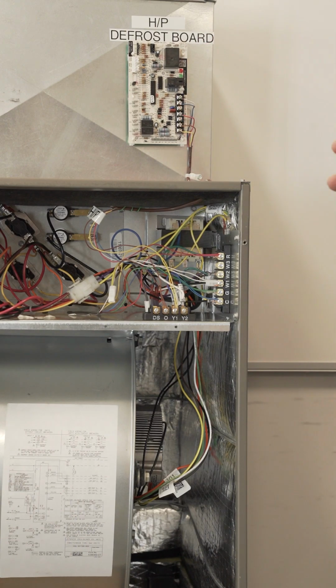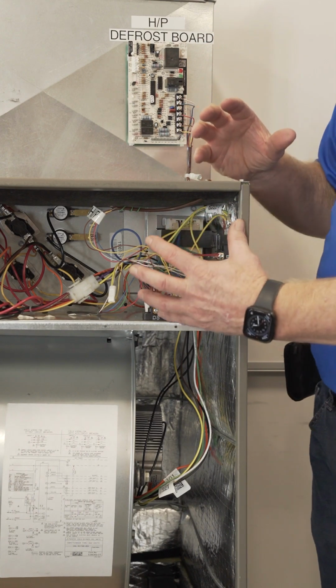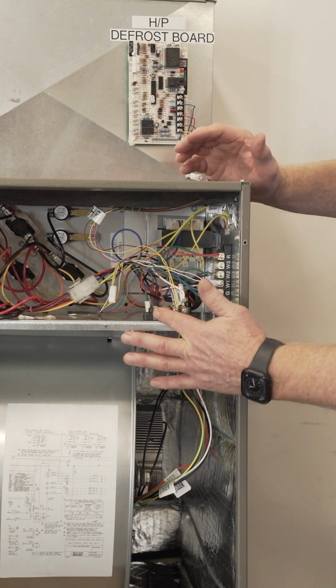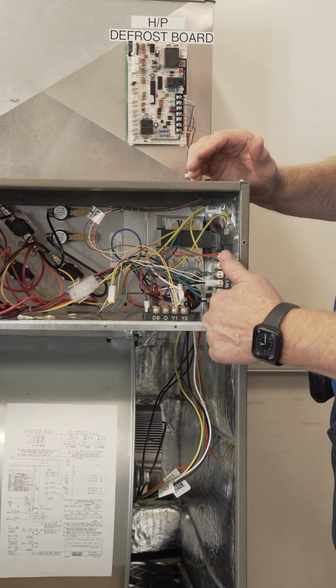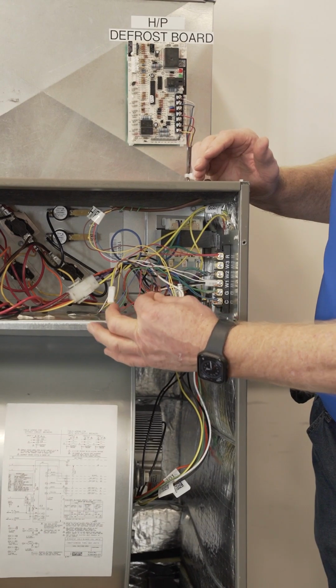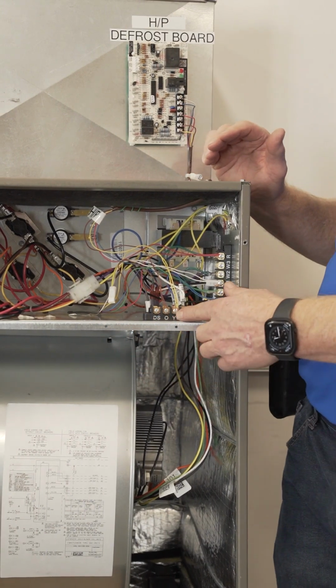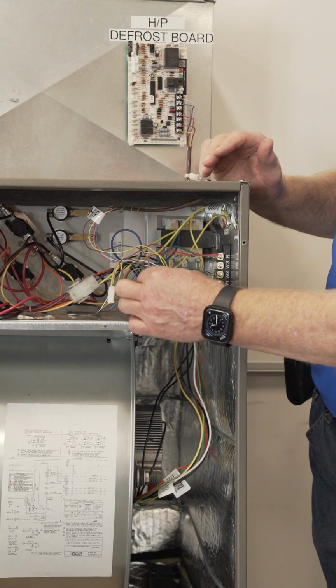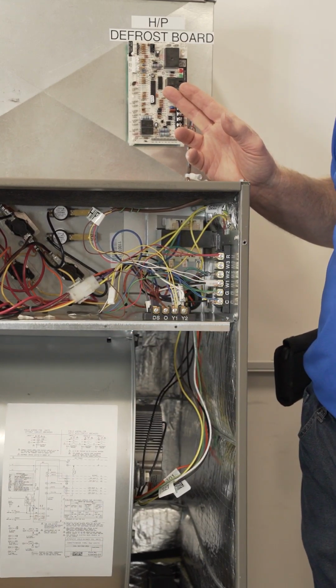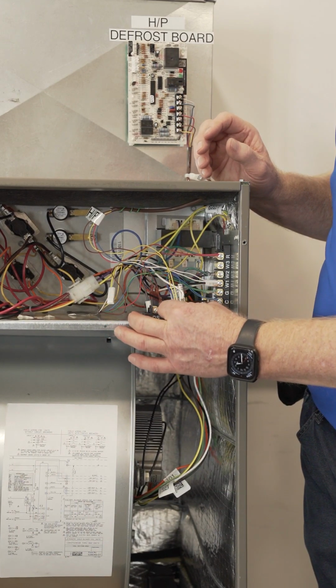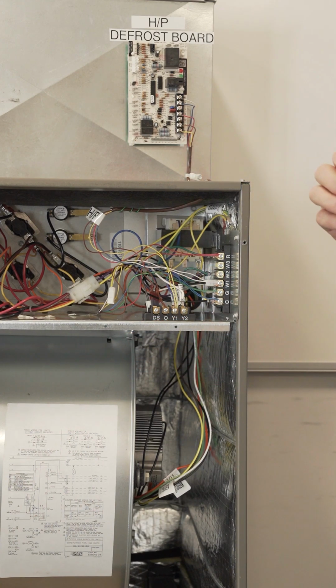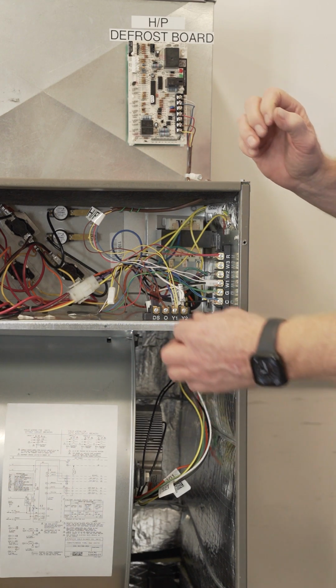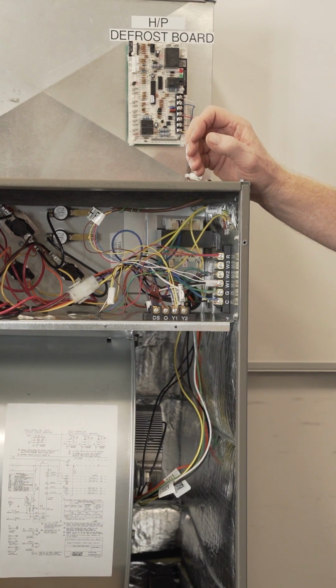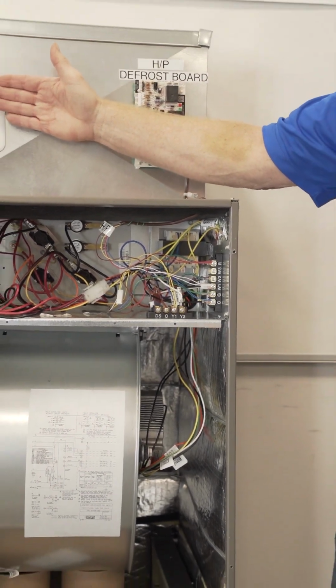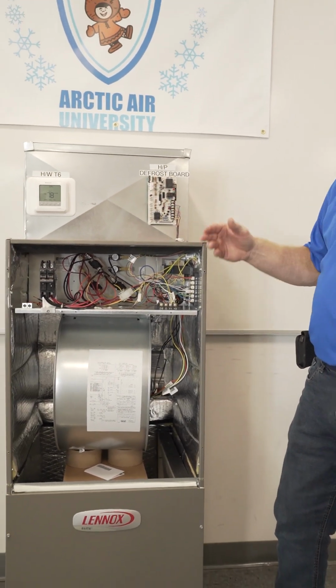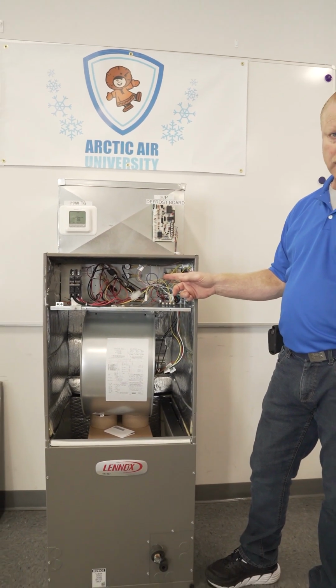All right, now our next system, we bring it all back together in here. This one, we have our terminal strips on the front here and on the side. A lot of units do not have an O terminal. This one does. So I used brown for O on this particular one. I attached both of those to that screw, and that's just my junction point for that. If you do not have an O, you basically wire nut that together, because you're going from your thermostat right out to your defrost board. Your wire nut is your junction in here.